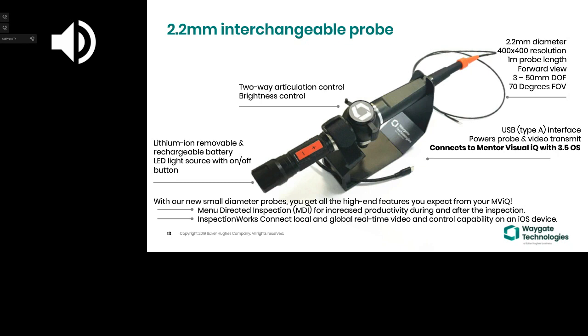So you'll be able to get into a lot of areas you weren't able to before unless you used our Borescope adapter, which is still available, and you can clip other optical instruments like some of our fiber scopes are actually a 0.5 millimeter OD. So the possibilities there, but this is a really nice package with two-way articulation. It has field replaceable, rechargeable lithium-ion batteries down in the small end of the handle.